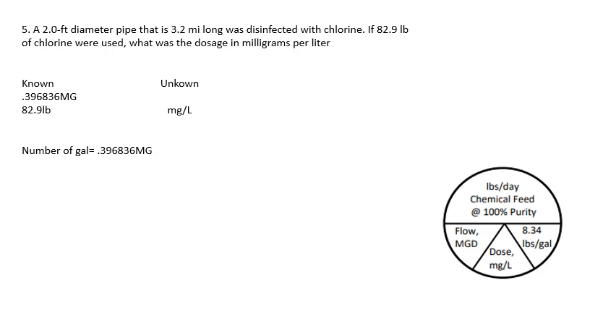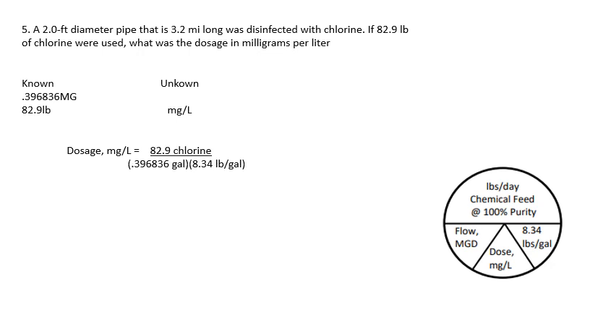To get dosage in milligrams per liter, divide the pounds of chlorine by million gallons times 8.34 pounds per gallon. Note: this is total volume, not flow per day. Plug in: 82.9 divided by (0.396836 times 8.34) equals 82.9 divided by 3.31. You get a dose of 25.05 milligrams per liter.